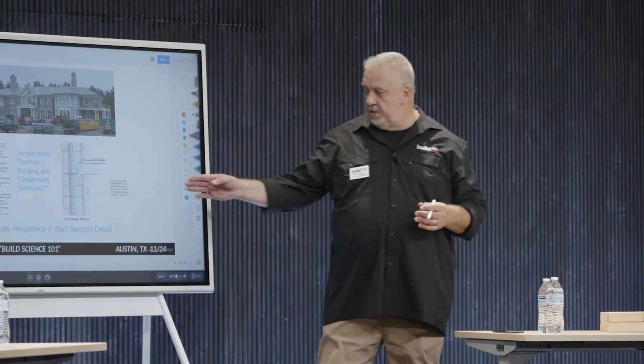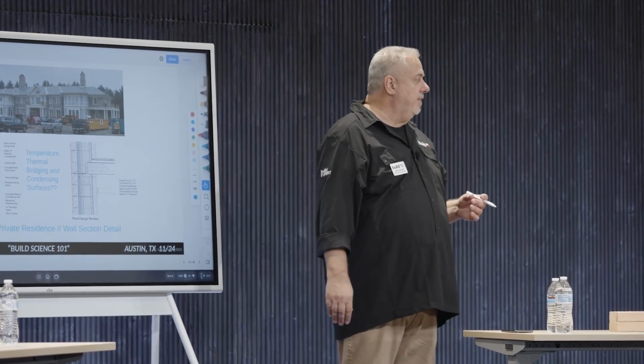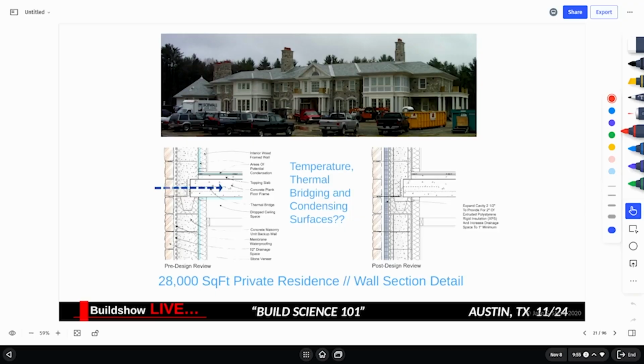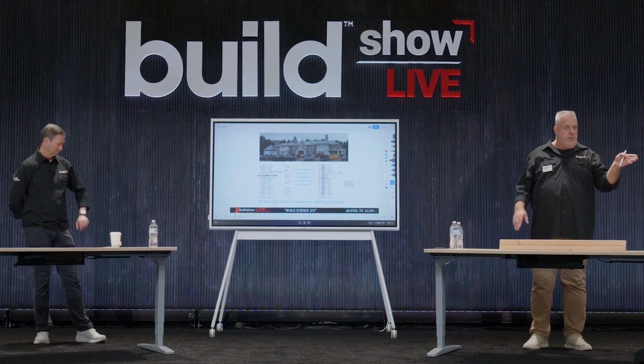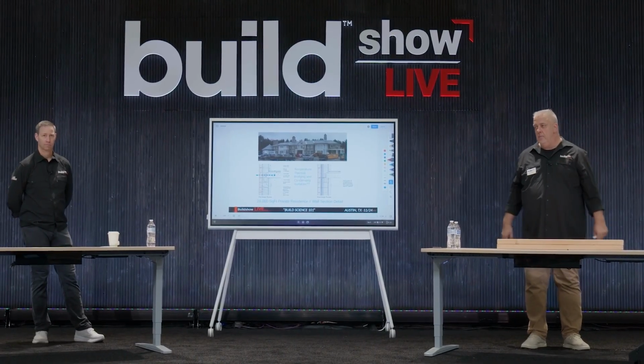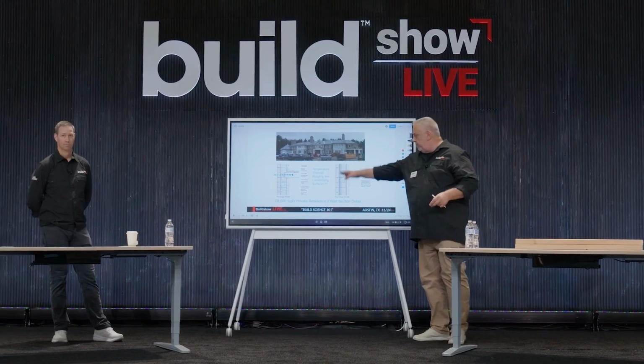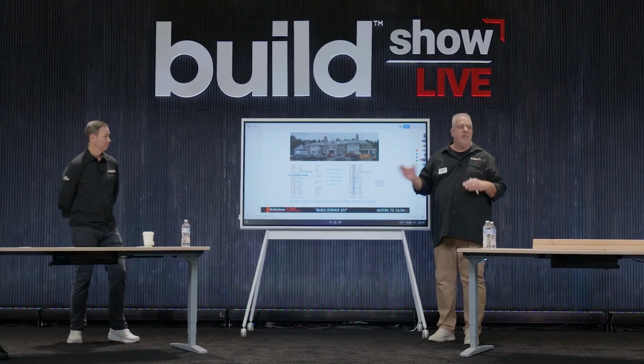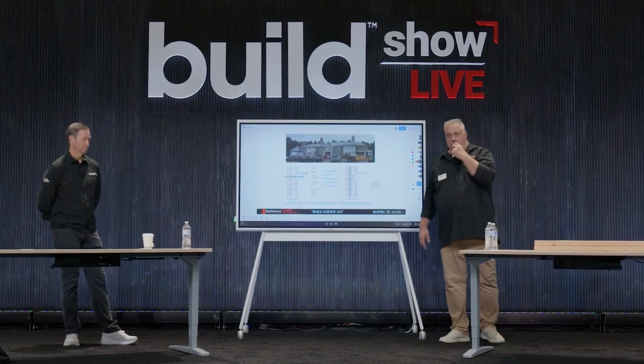So the solution was we thermally break the whole system on the outside. Now, when it comes to condensation, understand it's the difference of 1 degree, right? When you look on the psychrometric chart, it doesn't take a lot to go from vapor to liquid water. 1 degree. So while this might not be the best performer for insulation, we elevated that temperature enough to get us out of that risk of condensation.